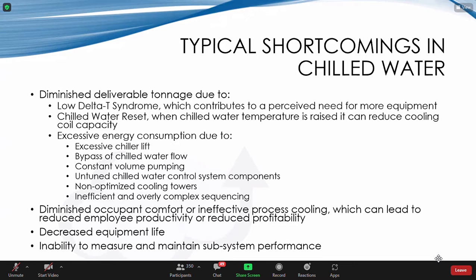So these are some of those: excessive energy consumption due to excessive chiller lift, bypass of chilled water flow, constant volume pumping, untuned chilled water control system components, non-optimized cooling towers, and inefficient, overly complex sequencing.